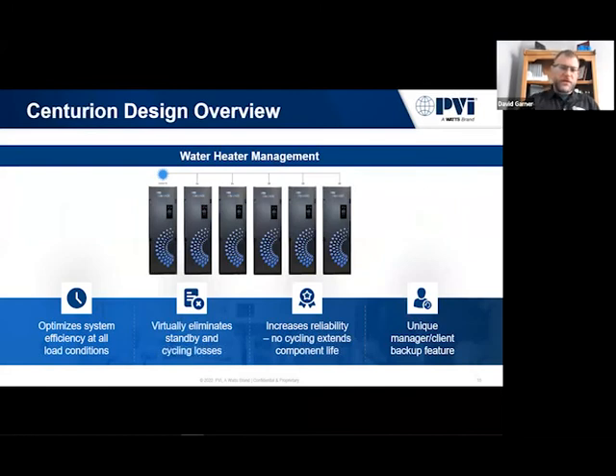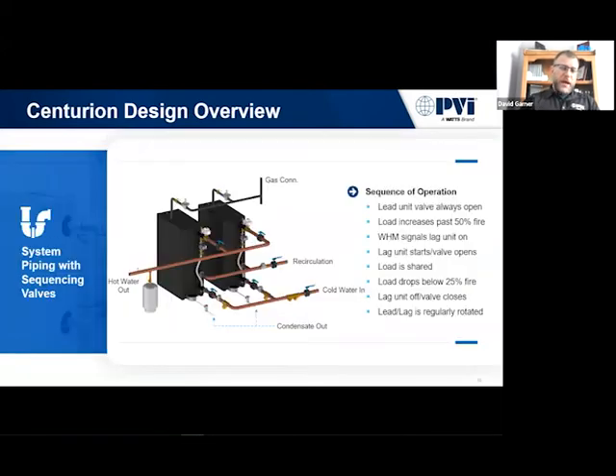When we start looking at the units themselves, we have a water heater management. So when I mentioned that we're going to have up to 16 units talking to each other, we can have up to 16 units that communicate with each other, and the units themselves have the ability to sequence. So just on these couple units we have right here, it's kind of hard to see in this picture, but there's valves that we have on the outlet of the unit. In this scenario, our default logic always has one valve open, so we don't accidentally deadhead a recirc pump.